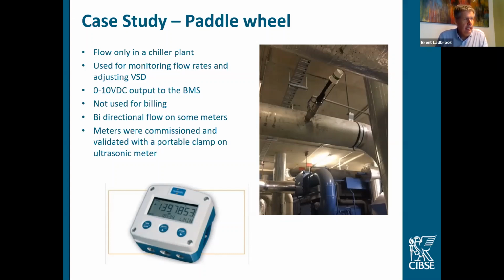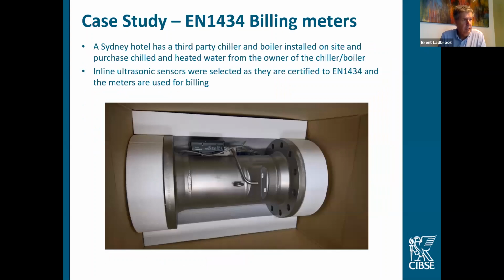They used analog signals, so there's no real diagnostics available out of this, and they were working at the time of commissioning accurately. Are they still? We don't know. We don't have any diagnostics whatsoever. I guess we presume they are, but they could be recommissioned.